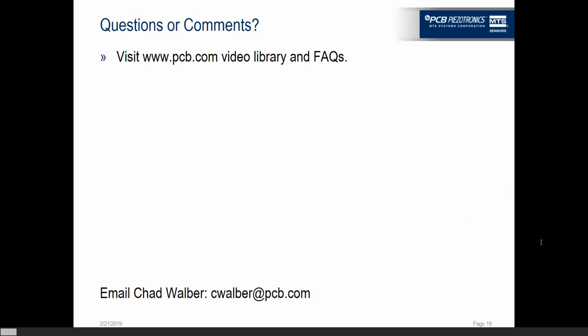Now, I will say this at this point: for calibrating other apparatus, please, please check with your specific standards. If you're being held responsible for calibrating something, it is completely up to you to make sure that you're calibrating it right. So I always tell people, and highly recommend, that they own the standards to which they should be calibrating. We own here at PCB all the standards with which I calibrate, and I actually sit on the standards committees for microphone calibration. So I basically have an open book to all that information.